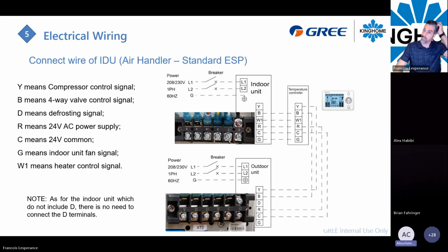Okay. So it's powered from R then, so it always has power, and then we'll send it out. Okay. So at the R terminal here there's a relay inside on the board somewhere, and this relay will be active during the defrost. So the R here will be jumped directly to the D terminal, and this D terminal hooked on the W1 will provide the call for the heat.